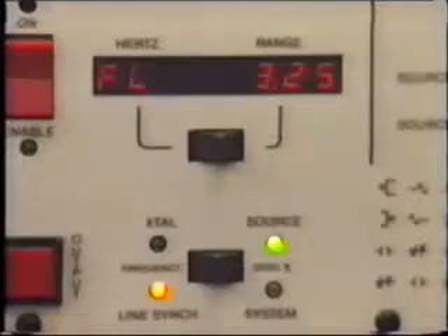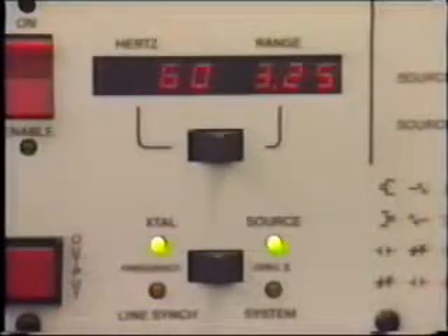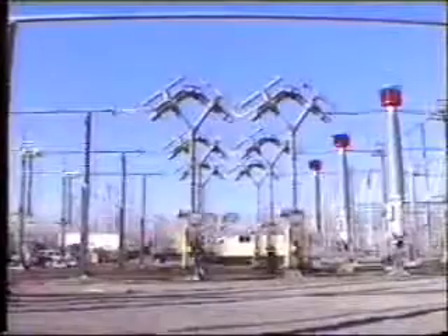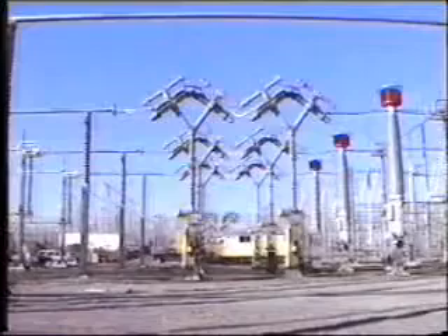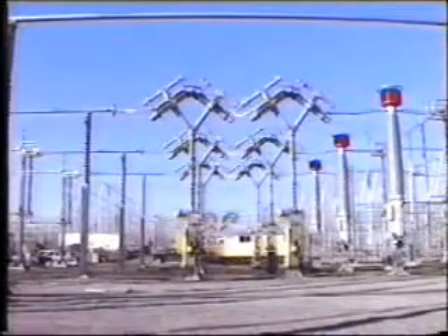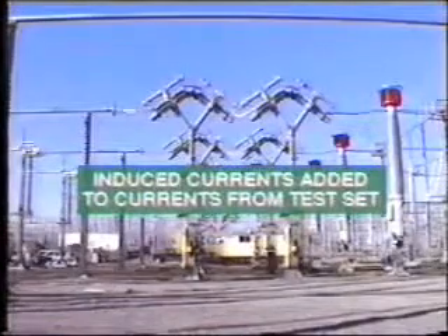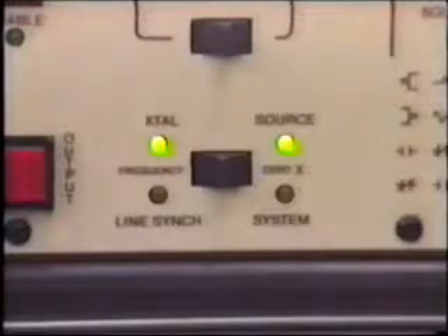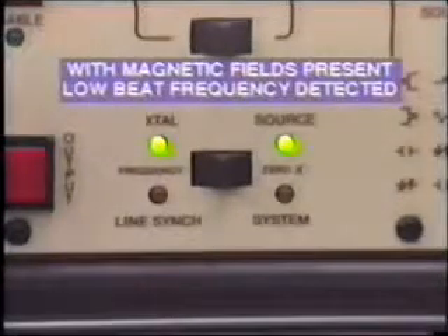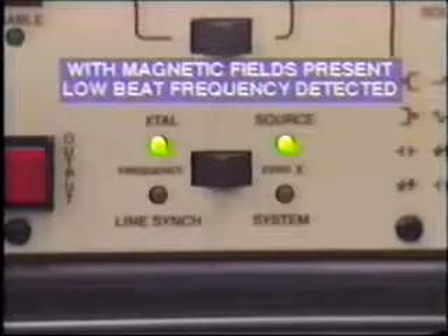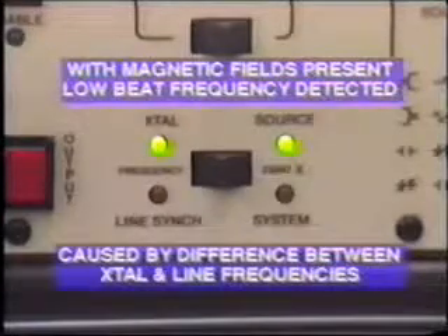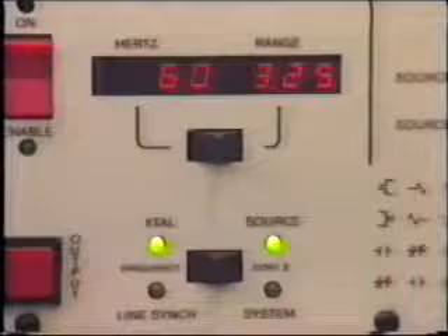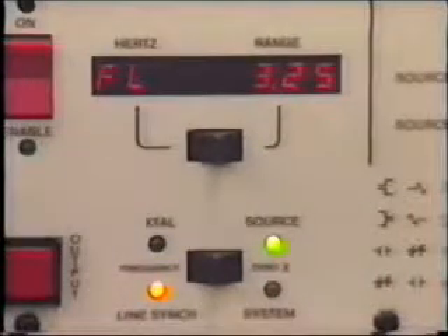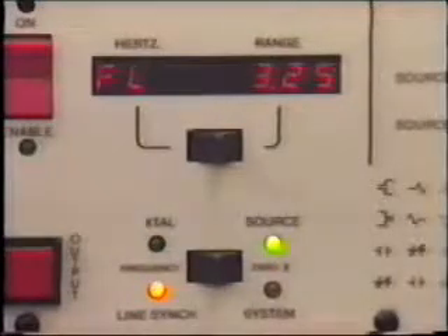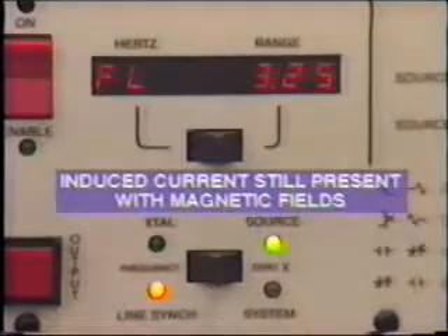The test set outputs can be selected by this switch to synchronize with line frequency, or to be referenced to an accurate crystal which permits variable frequency operation. When relay testing is performed in an environment where 60 Hertz magnetic fields are present, it is possible that stray induced currents may be added to the currents from the test set. When the test signals are referenced to the crystal time base, a low beat frequency may be detected in the relay response. This beat frequency is the result of the small difference between crystal and line frequencies. By switching to the line sync position, this beat phenomenon can be eliminated. However, this does not mean that the induced current has been canceled, and test results may be affected by the unwanted magnetic field interference.